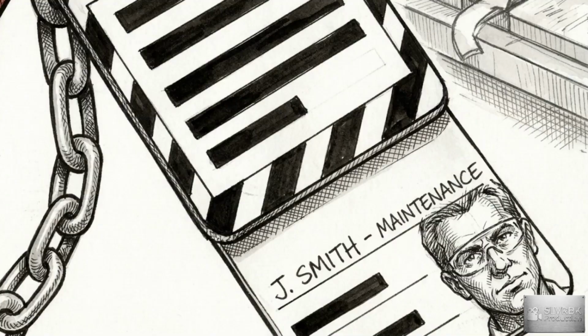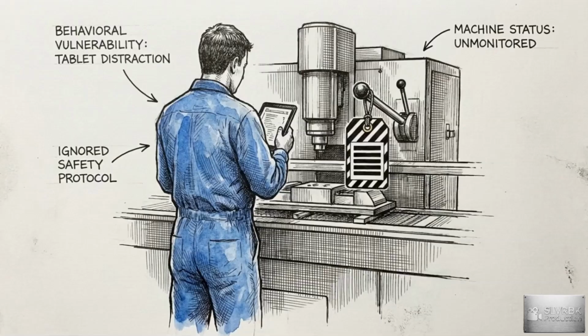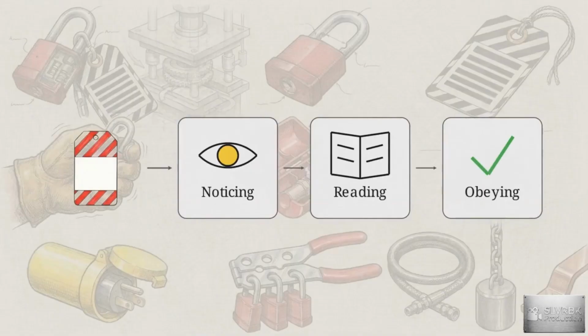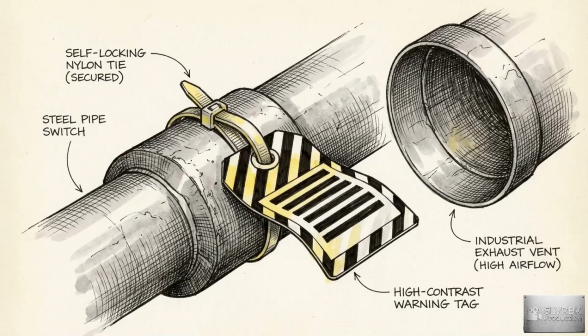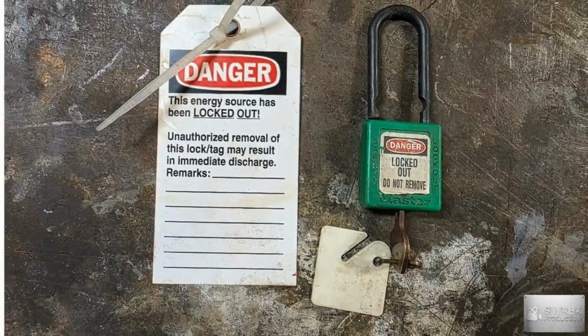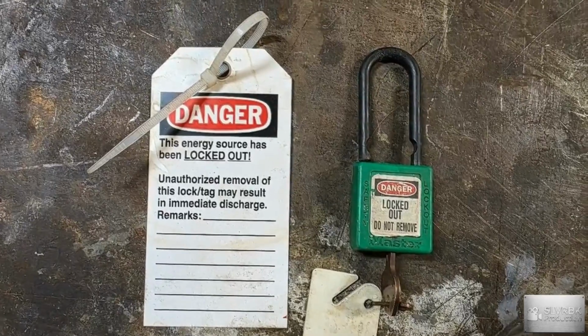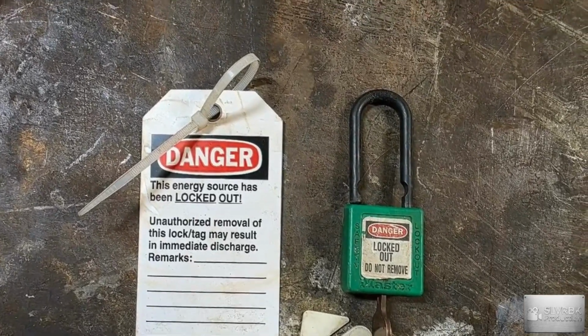Each tag must also clearly identify the specific authorized employee who applied it, removing any ambiguity about who is actively working on the equipment. However, OSHA explicitly warns that tags evoke a false sense of security. Because they lack a physical barrier, their effectiveness relies entirely on every single employee noticing, reading, and obeying the warning. To prevent a tag from simply falling off or being casually brushed aside, the regulation mandates a physical fail-safe. The attachment must be a non-reusable, self-locking nylon tie with a minimum unlocking strength of 50 pounds.